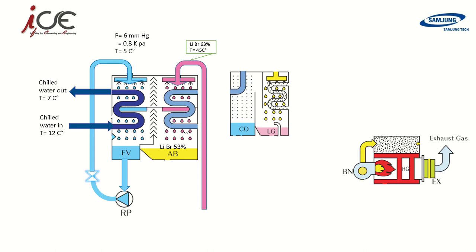With the increase in temperature of lithium bromide, its ability to absorb additional water vapor decreases. So it must be cooled in order to increase its absorption capacity again and withdraw the largest amount of vapor. This is the importance of cooling water coming from the cooling tower — to cool the lithium bromide solution in the absorber first and then in the condenser. The cooling water enters the chiller at a standard temperature of 32°C and exits the chiller at 37°C.